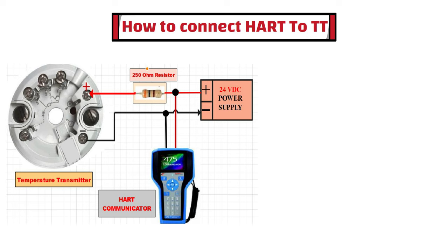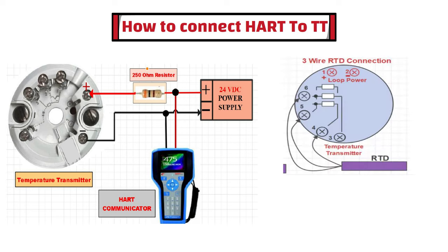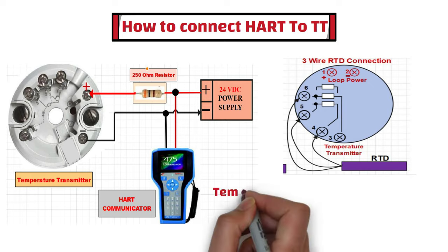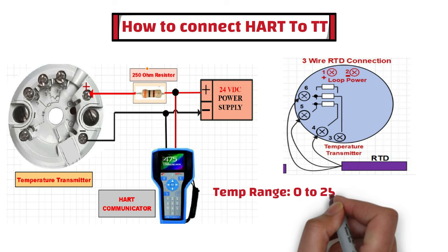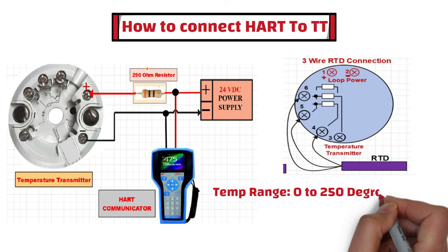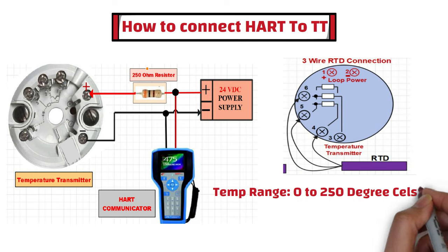In this example, let's assume that a 3-wire Platinum 100 RTD has been connected to the temperature transmitter, and that a 0–250 degree Celsius range needs to be set in the temperature transmitter.